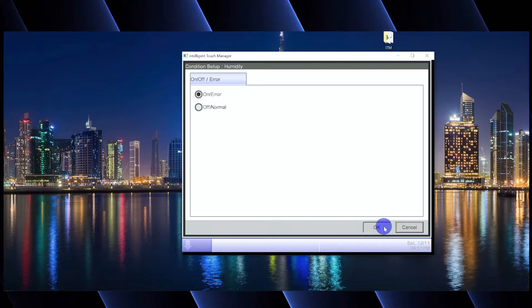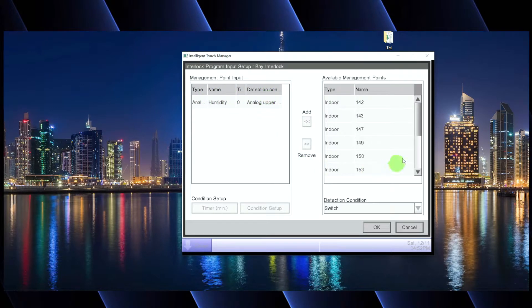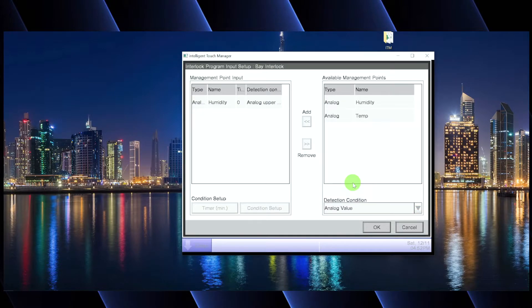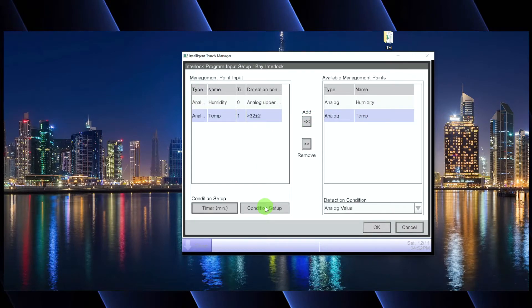So if the upper limit enables and that point alarms, we enter this condition. But we don't want to use just humidity — we also want to use temperature. So we go back to Modify and grab another point. This time we're going to grab analog value, because when we created this temperature point we never created an upper analog limit. So we grab that, move it over, and create a conditional setup.